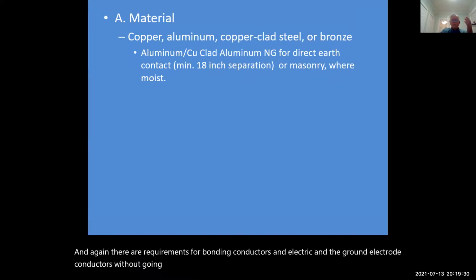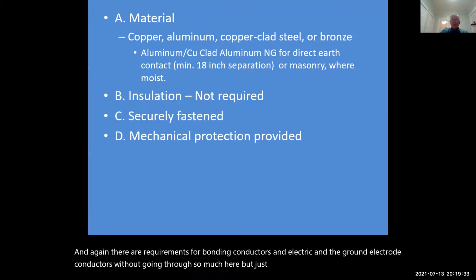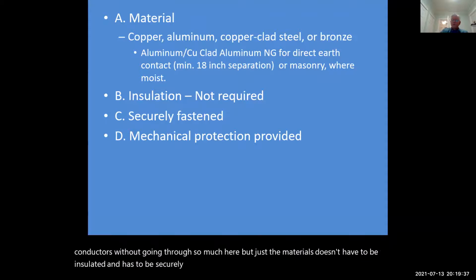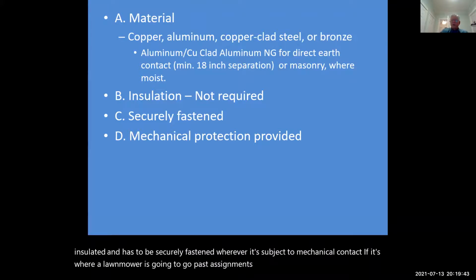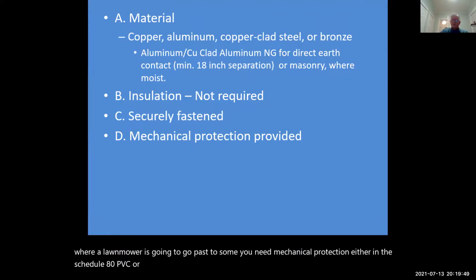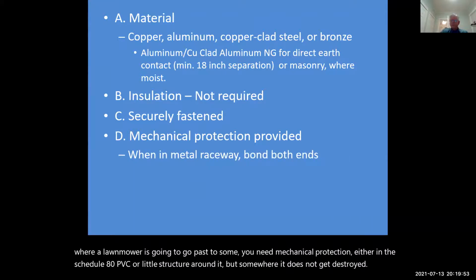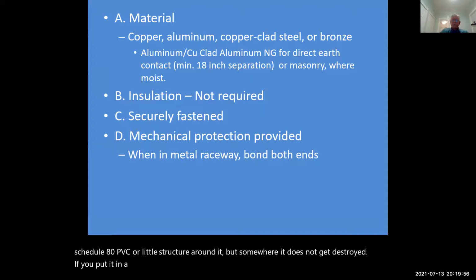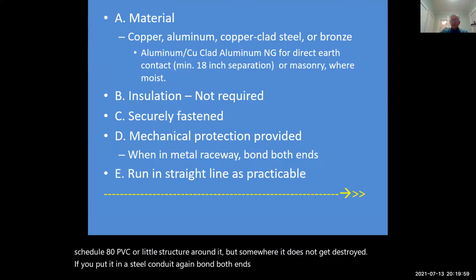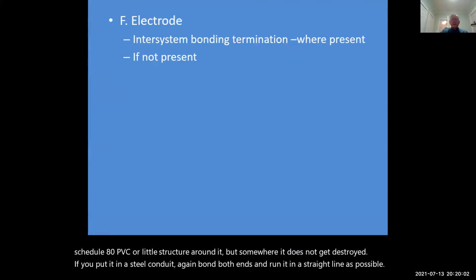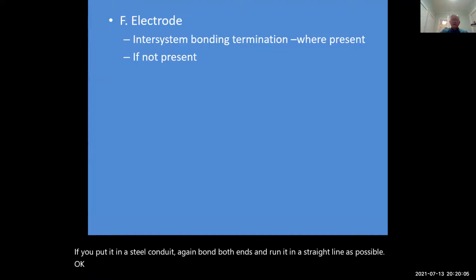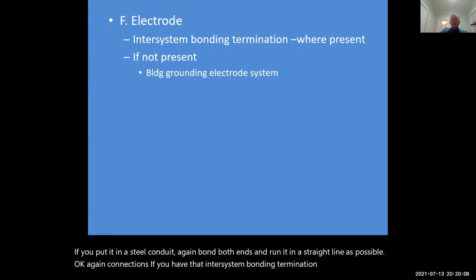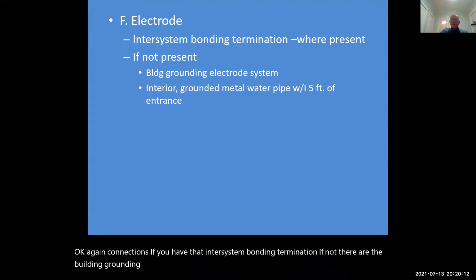Without going through so much here, just materials: it doesn't have to be insulated, it has to be securely fastened. Wherever it's subject to mechanical contact, if it's where a lawnmower is going to go past or something, you need mechanical protection, either in Schedule 80 PVC or a little structure around it, but somewhere where it does not get destroyed. Putting it in steel conduit, again, bond both ends and run it in as straight a line as possible. And again, connections, if you have that intersystem bonding termination. If not, there are the building grounding electrode system, grounded metal water pipe, 5 feet from where it comes in, and so forth.